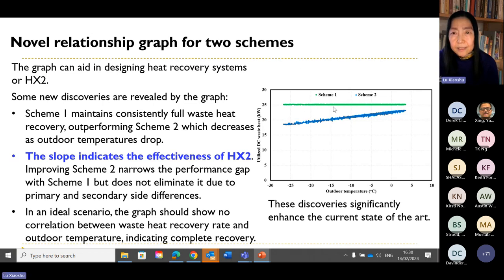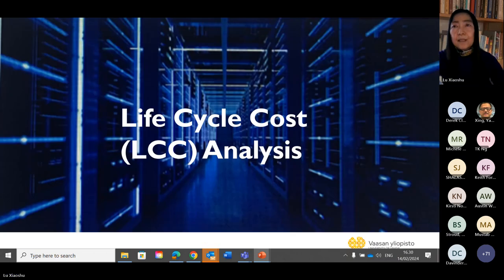In an ideal case, as shown in the horizontal line for scheme one, the graph should show no correlation between waste heat recovery rate and outdoor temperature, indicating complete recovery. So these new discoveries can be used to help design and plan energy efficient heat exchangers, so you can adjust the effectiveness.